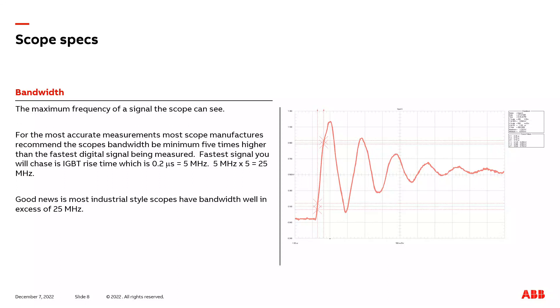The fastest event on a VFD that you will be attempting to measure with the scope is going to be the IGBT rise time, which is 0.2 microseconds, which converts to five megahertz. If you take five megahertz times five, you get to 25 megahertz. So your scope has to have a minimum bandwidth of 25 megahertz. Well, the good news in the marketplace today, almost all scopes have a bandwidth well in excess of 25 megahertz, many of them into the hundreds of megahertz. So you shouldn't have too hard of a time finding a scope that meets the bandwidth requirement.